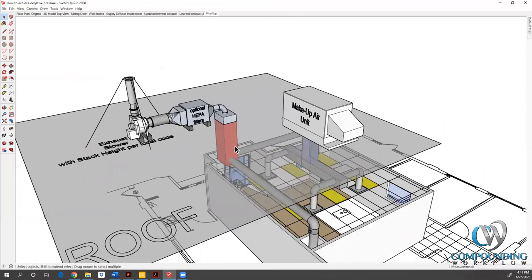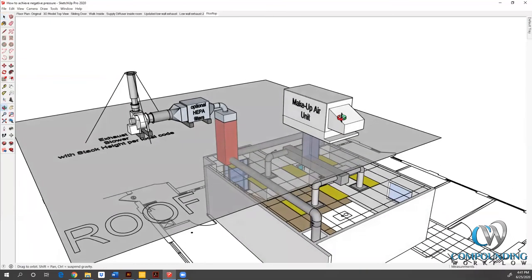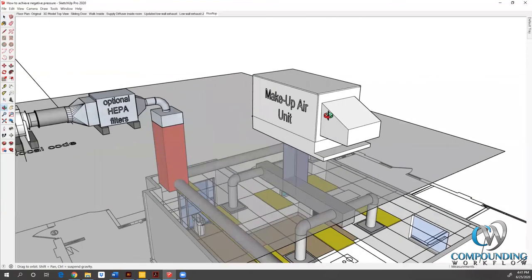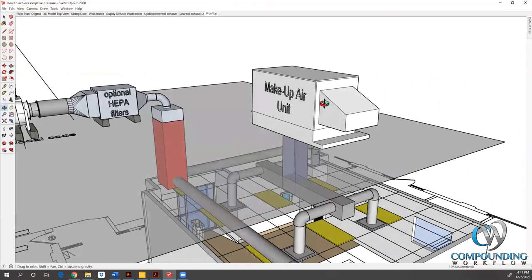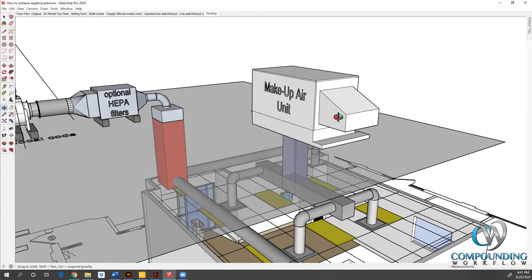Now what's supplying that original 1200 CFM is this makeup air unit. I've told you before in other videos, and I've said it many times at conferences and white papers, that if you constantly and consistently throw air out of a building per USP 800, quote unquote the CSEC, the secondary engineering control, which is the room, is externally vented. That means you're throwing perfectly good air out of the building. You cannot rob Peter to pay Paul and pull it from other places. It's not going to happen or your entire building is going to go negative.